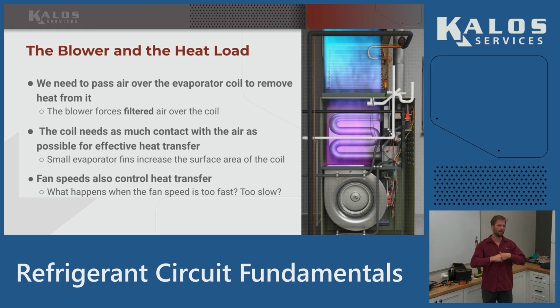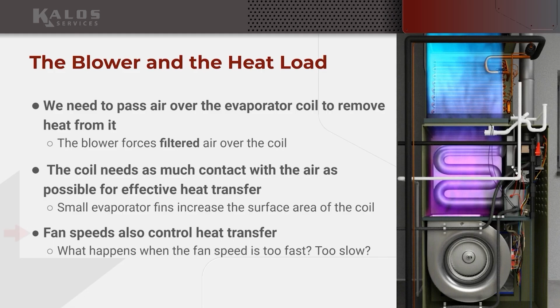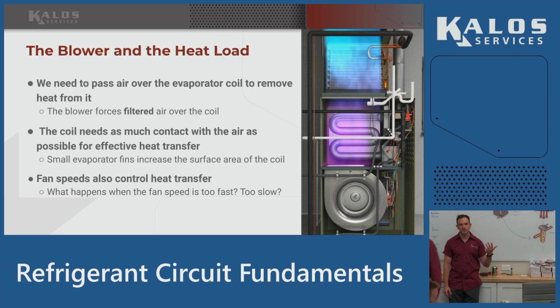It's creating turbulence. So even more of the molecules of the air and the moisture in the air are making contact with the metal surfaces. So the fan speed is also an important part of this. If you guys have seen those, the motors inside the air handlers, they've got multiple speed taps. Furnaces are a little different, you have fewer options, and then there's the variable speed ones which decide what speed they want to run on their own. They don't care what you say. But with the speed taps, you can set the speed of the blower, and you'll see that reflected in the pressure.